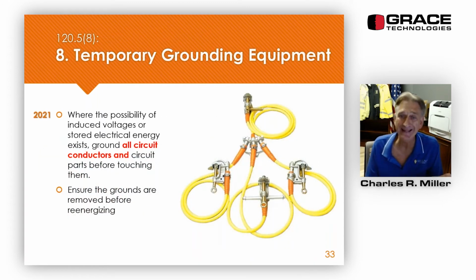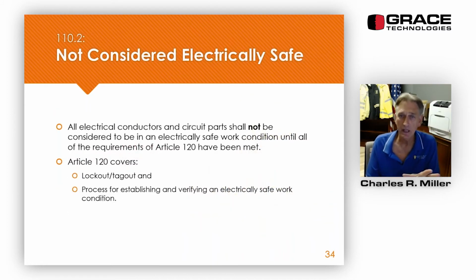All right, here's step number 8, and this is typically not done on less than 1,000 volts. These are temporary electrical safety grounds where the possibility of induced voltages or stored electric energy exists. Ground all circuit conductors and circuit parts before touching them. Ensure the grounds are removed before re-energizing. Absolutely.